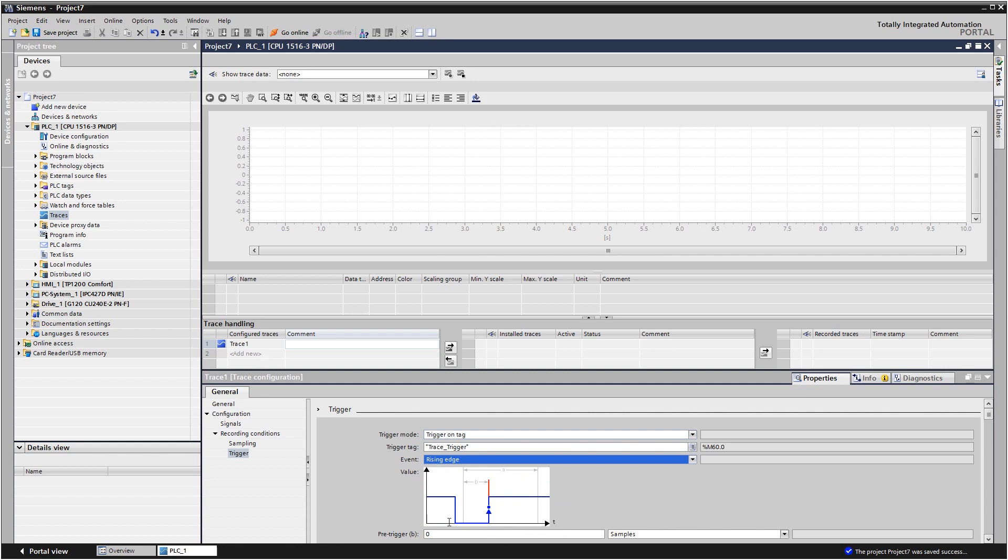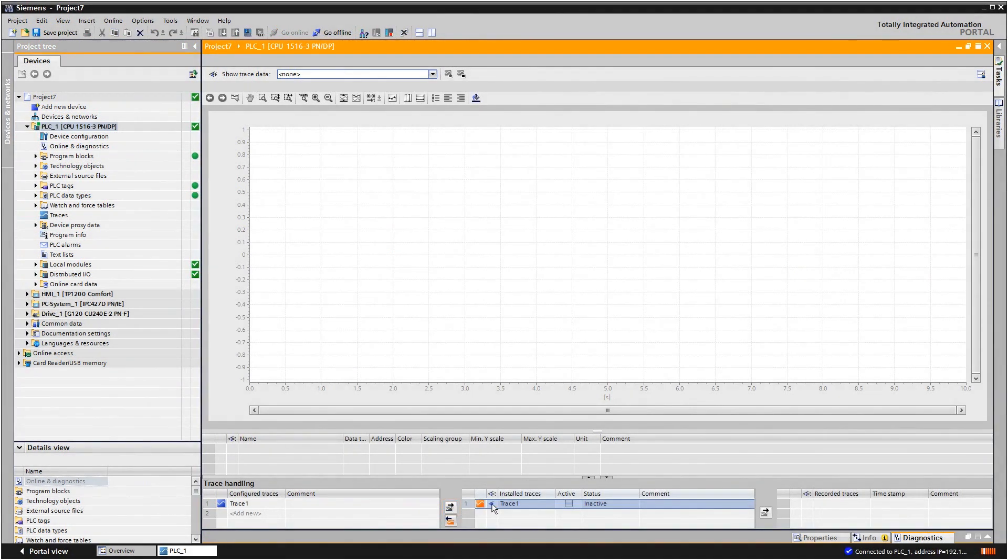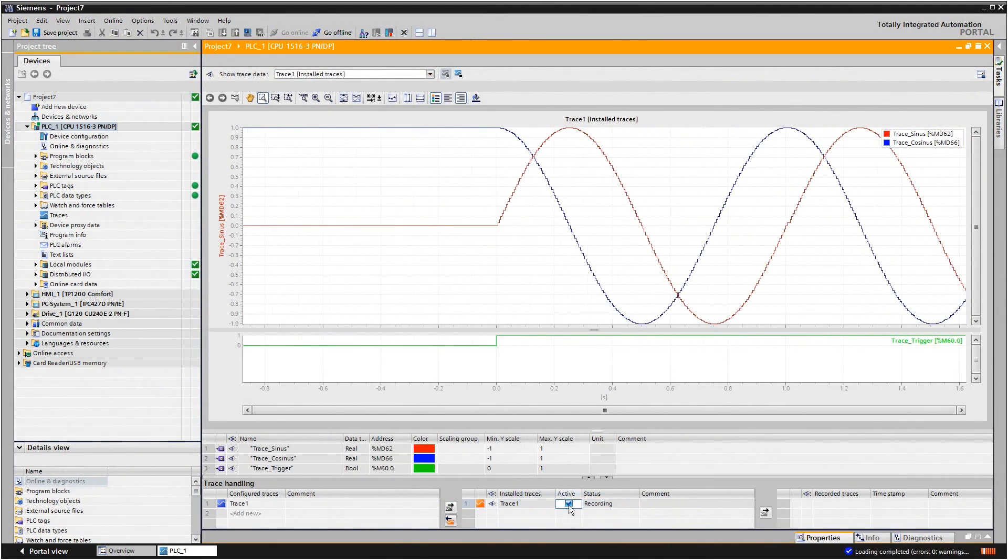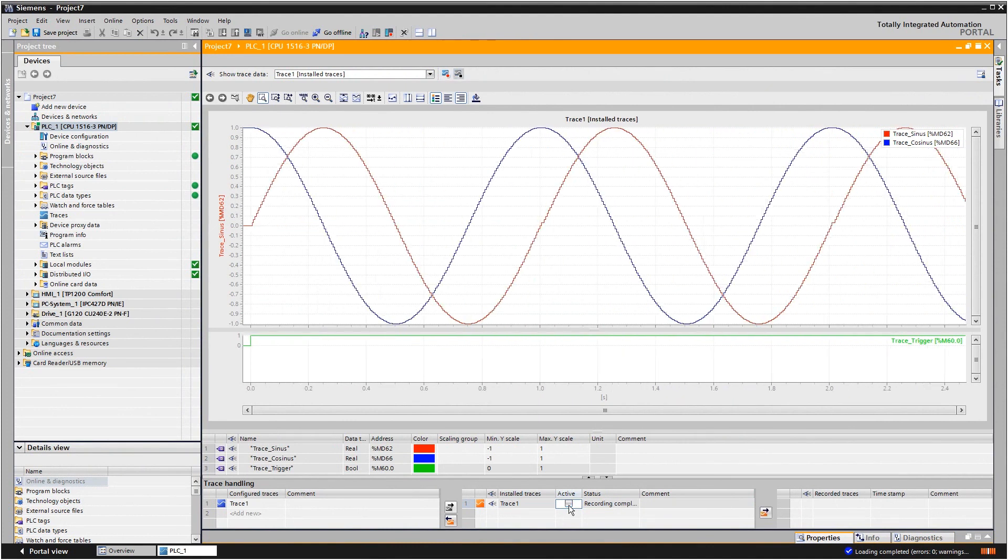With the pre-trigger function, you can record events before the trigger condition. Transfer the trace configuration to the device and activate the recording. The controller firmware does the rest. The recorded values are now loaded from the controller and displayed in a curve diagram for analysis.